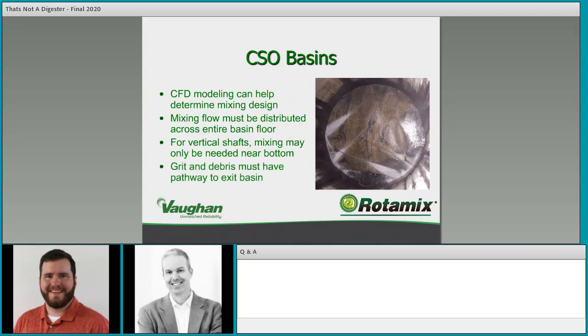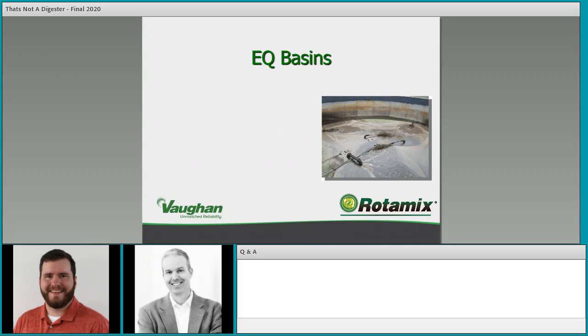Grit and debris must have a pathway to exit the basin. Even if you've got a large basin with debris spread across it, wherever your withdrawal point is needs to be a low point — an area where you can push the grit and debris so it actually has the ability to flow out. You need enough velocity as it's flowing out to keep it carrying through the system, or some ability to de-grit and screen so nothing stays in the CSO basin or in your piping.